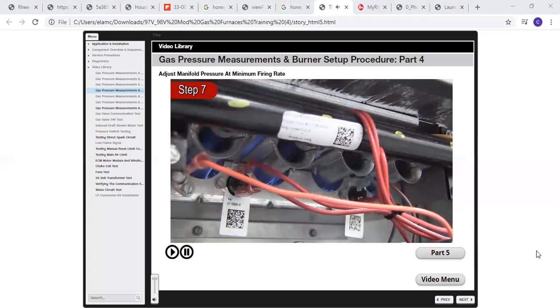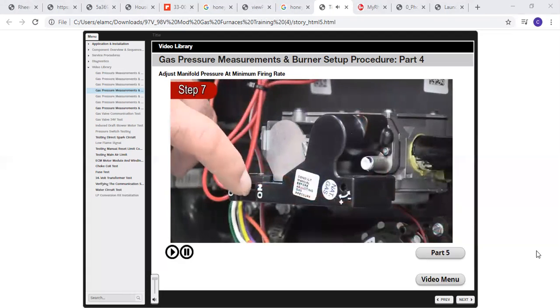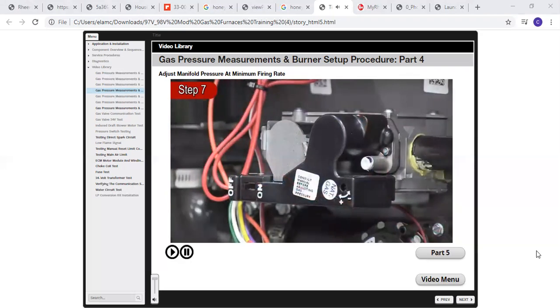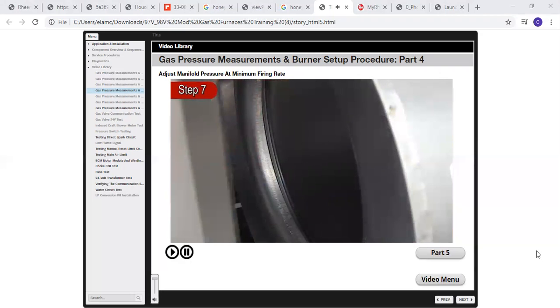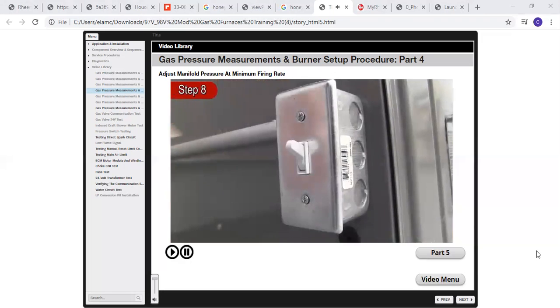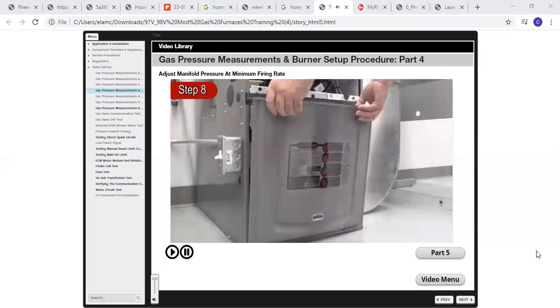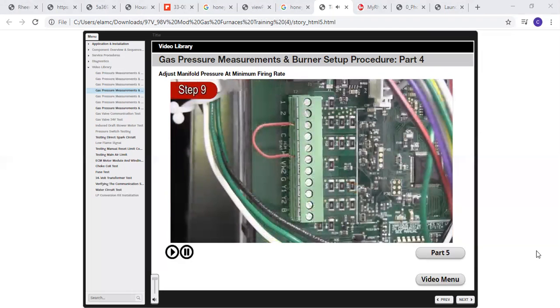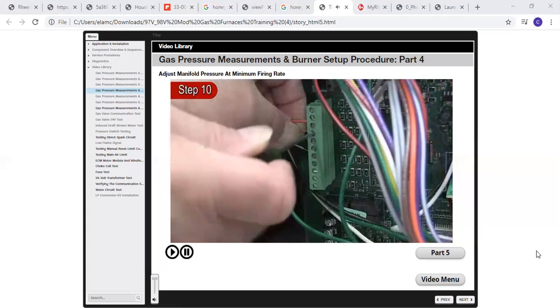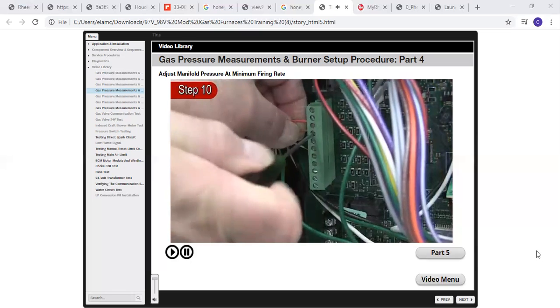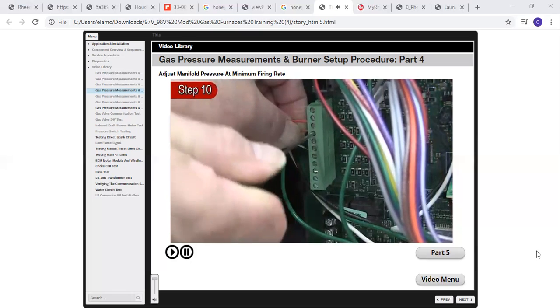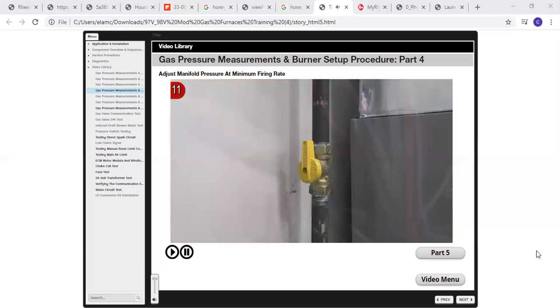Step 7. Once low fire manifold pressure has been adjusted, slide the gas valve on-off switch to the off position. Allow the indoor blower to complete off delay. Step 8. Disconnect electrical power to the furnace. Remove the blower door. Step 9. Remove the jumper across R and W1 to remove the heat call. Step 10. Reconnect thermostat wires. There should be no call for heat present at the thermostat.